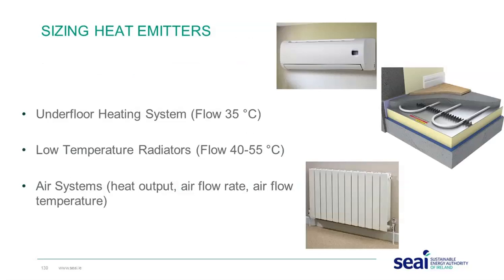Sizing heat emitters. When we look at heat emitters, we need to look at what type of heat emitter we have and what temperature they operate at. Typically, underfloor heating systems, we're talking about a flow temperature of about 35 degrees. Low temperature radiators can vary depending on the size of them, 40 to 55 degrees. And for air-to-air units, we need to look at the heat output, the airflow rate, and the temperature as well. Manufacturers will generally give you those details.